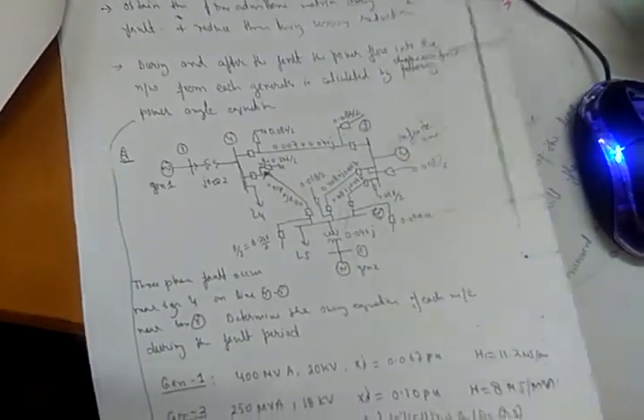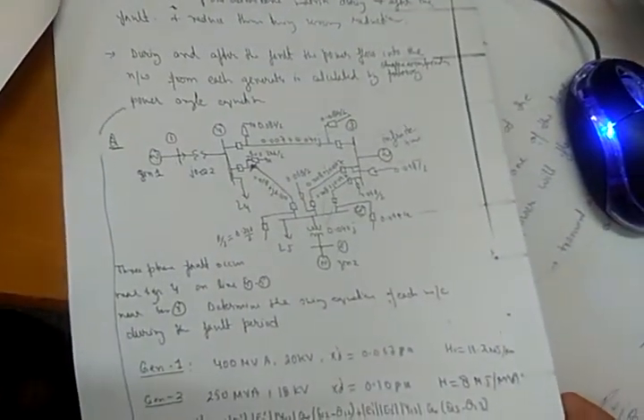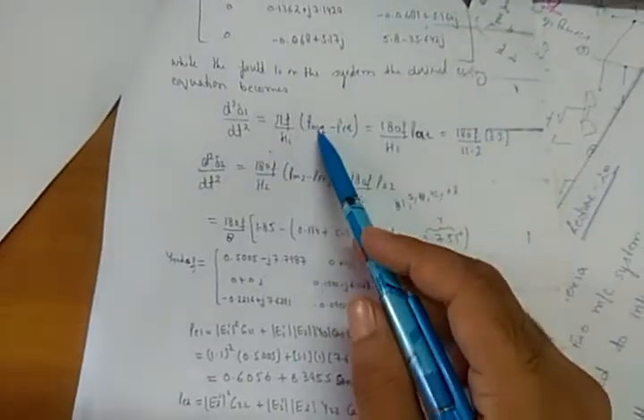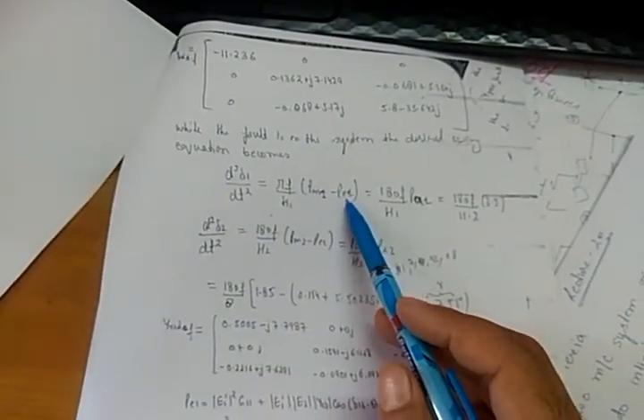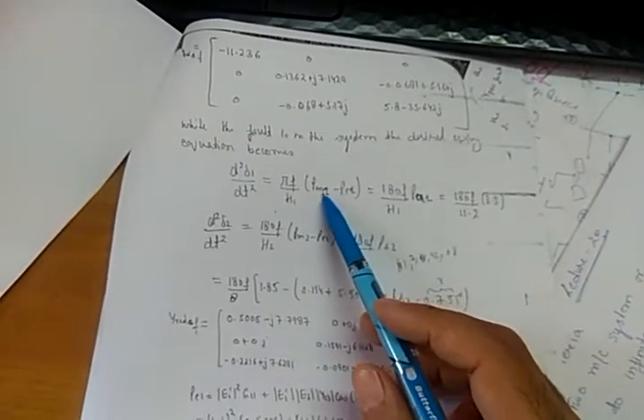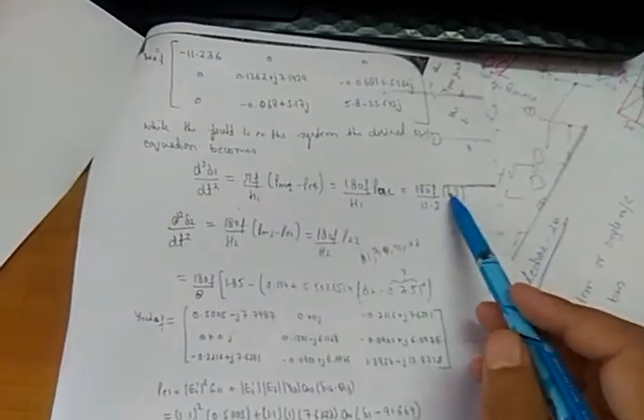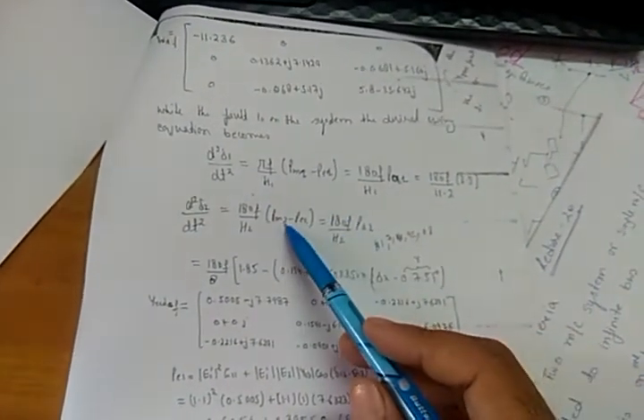What is P mechanical 1 and P mechanical 2? P mechanical 1 is 3.5 and P mechanical 2 is 1.85. Only because if you take P mechanical 1 equal to 3.5, then you will get this equation. Now, P mechanical 1 is 3.5 during the fault and P electrical 1 is 0, because at bus 4 we have 0 power. So the accelerating power will be equal to P mechanical 1, which is 3.5. P mechanical 2, I am saying, is 1.85, so 1.85 minus P electrical 2 here.